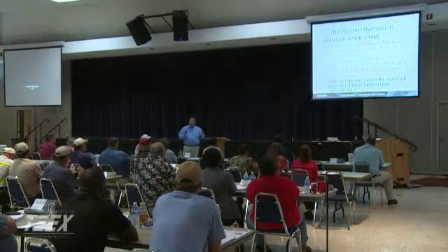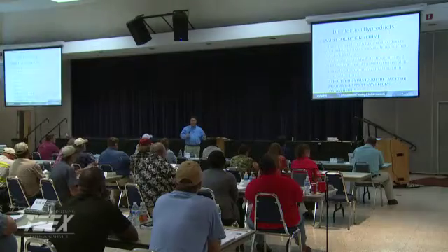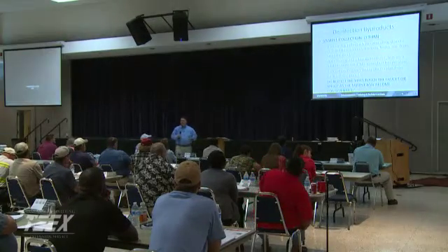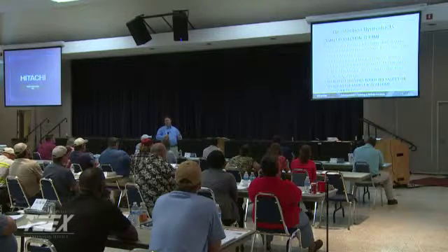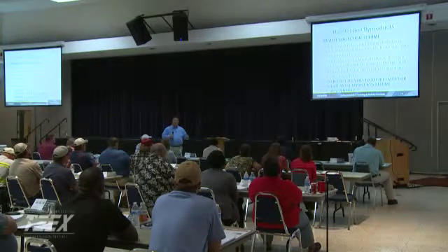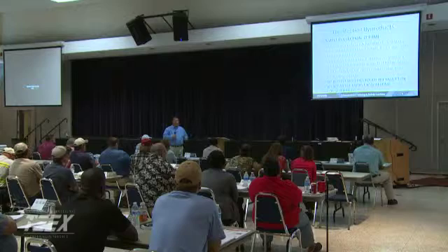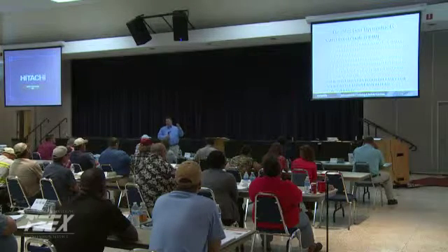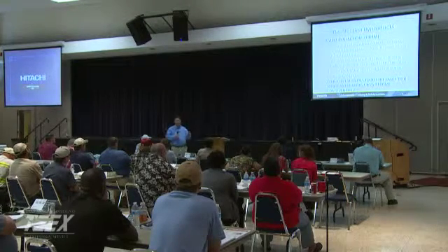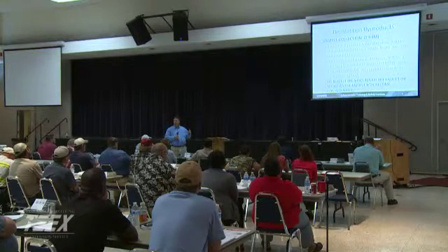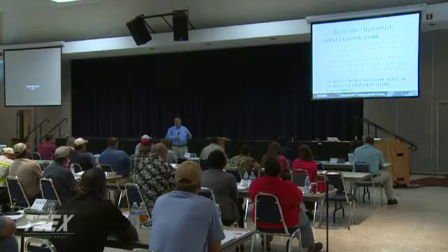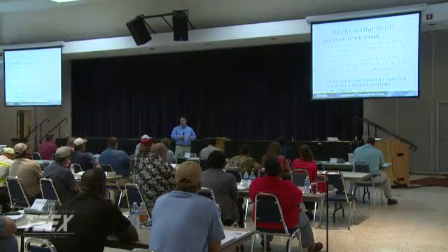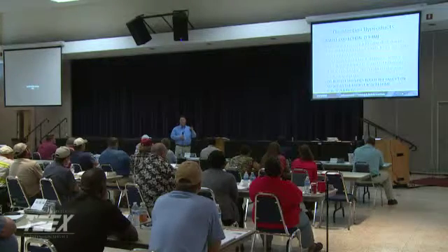Again, this can be very repetitive of the Bac-T sampling because it's a very similar process. To make sure that you're getting a representation of what's in the line, not what's sitting in that meter run or the customer's plumbing, let it run for a couple minutes. You can also put a temperature gauge in there, a thermometer, and check and see when you see a noticeable temperature change. That'll let you know that you're actually getting water from your system, from that distribution pipe, versus what's sitting in the meter run.